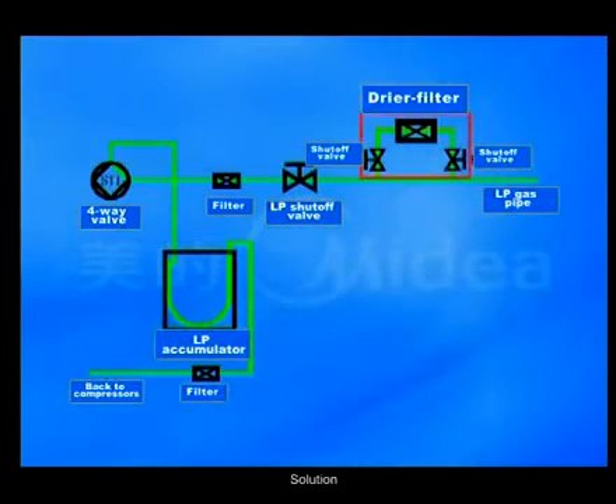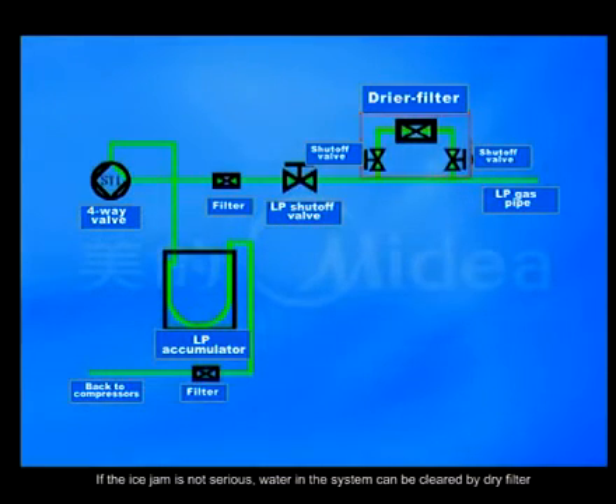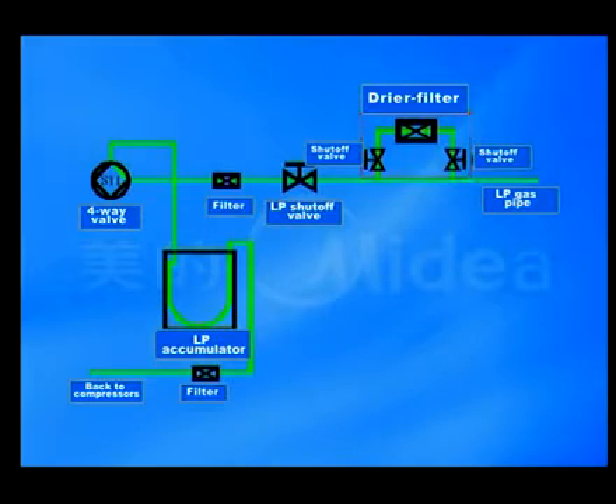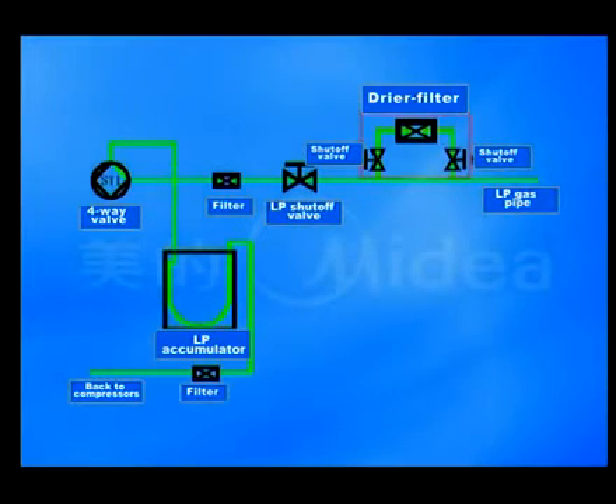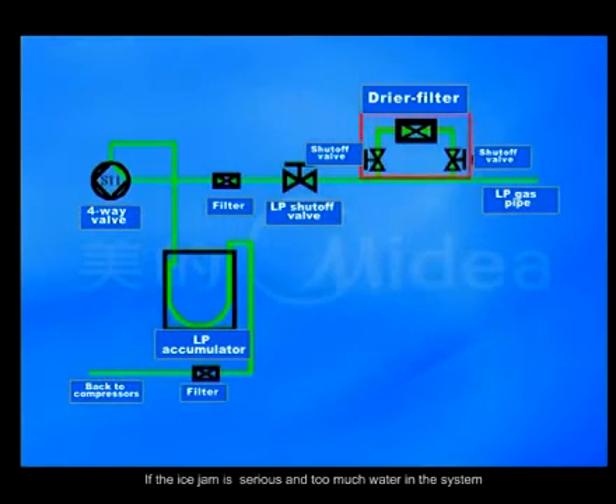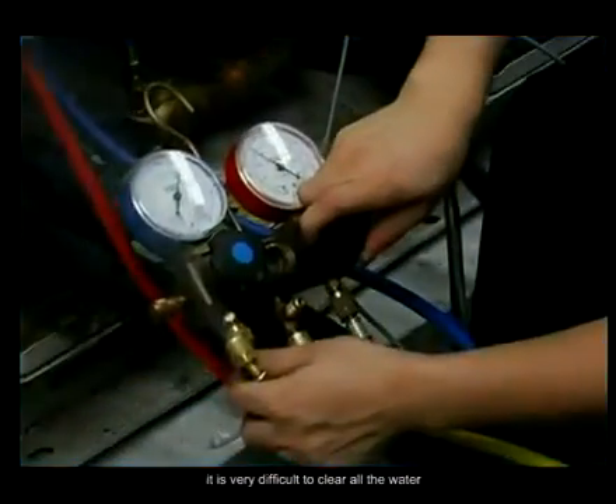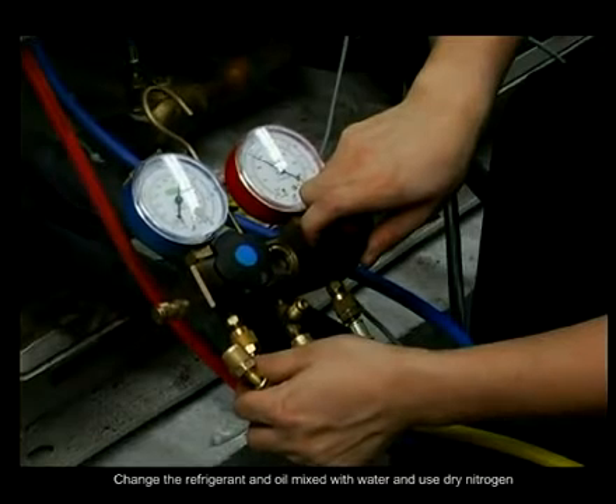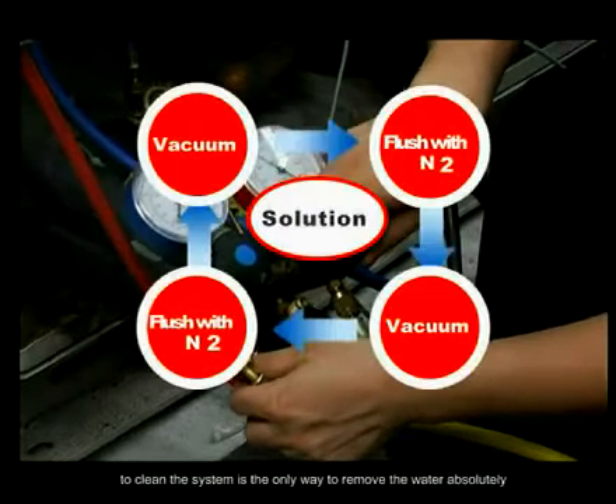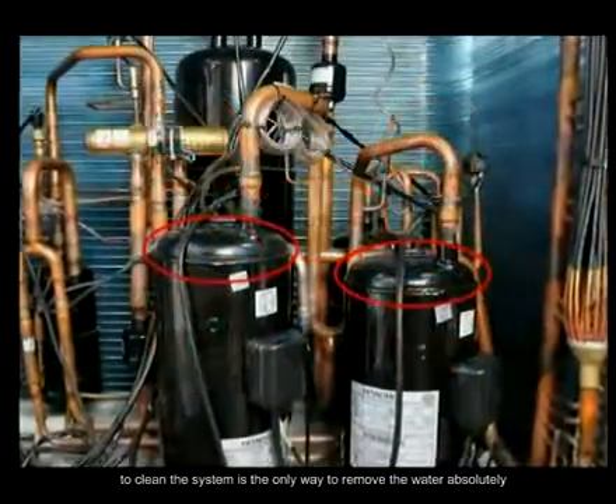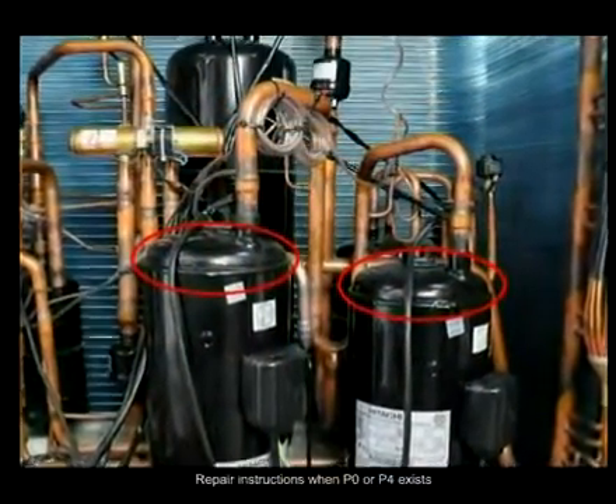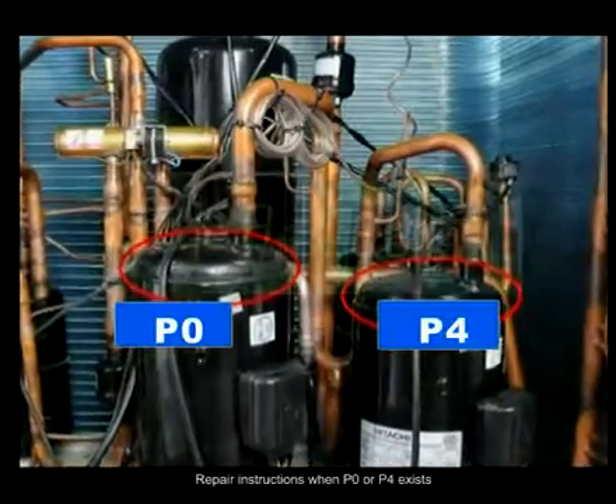Solution. If the ice jam is not serious, water in the system can be cleared by a dry filter. If the ice jam is serious and there is too much water in the system, it is very difficult to clear all the water. Changing the refrigerant and oil mixed with water and using dry nitrogen to clean the system is the only way to remove the water absolutely. Repair instructions when P0 or P4 exists.